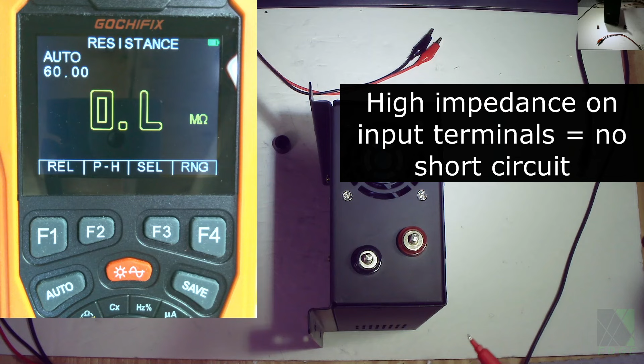What does that mean? The first thing we can determine is it is not a short circuit. What would a short circuit look like on an inverter like this? It would look something like this: if I probe one side of the terminal, you see all zeros—0.4 of an ohm, 0.3, really it's saying zero. But when I probe this inverter, I get something more like 469.9 kiloohms—that's thousands of ohms, 470,000 ohms. That cannot possibly be a short circuit.